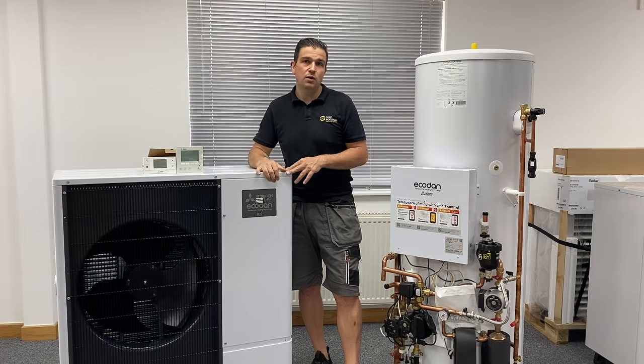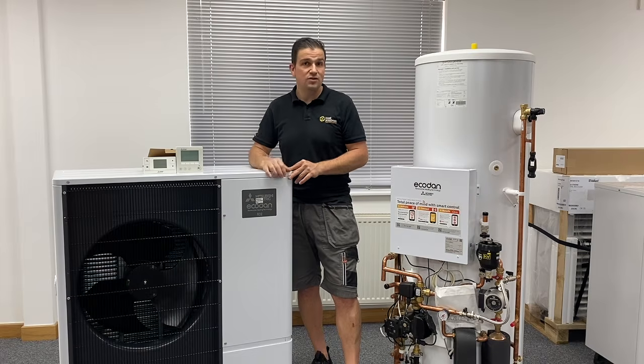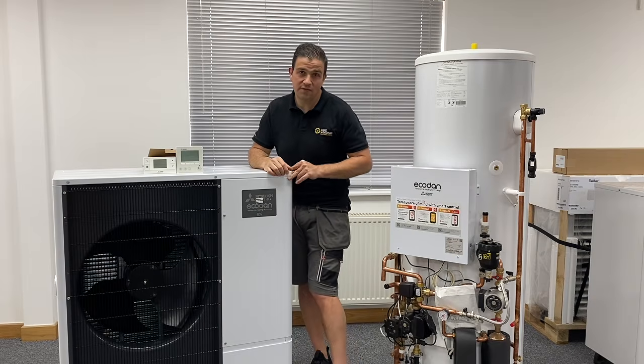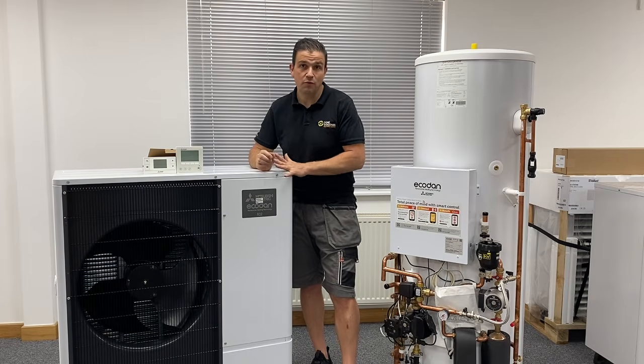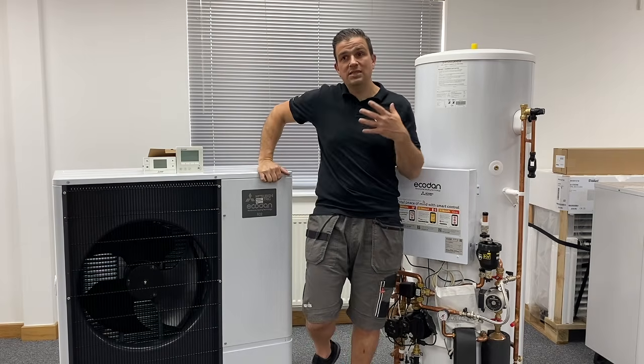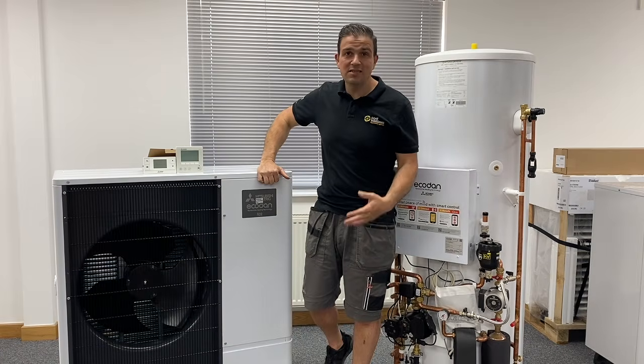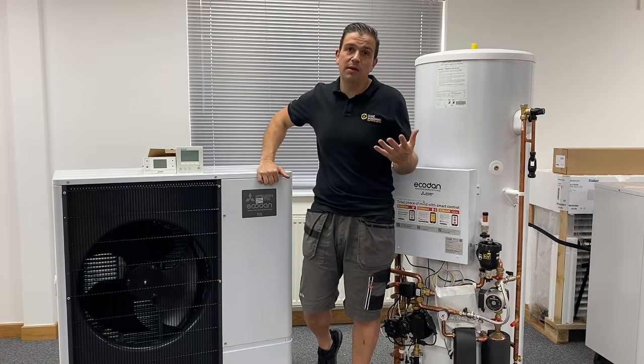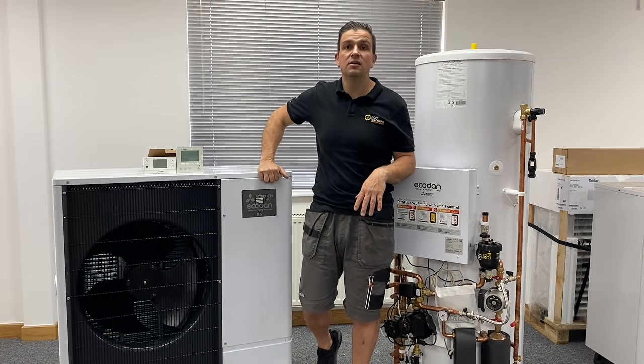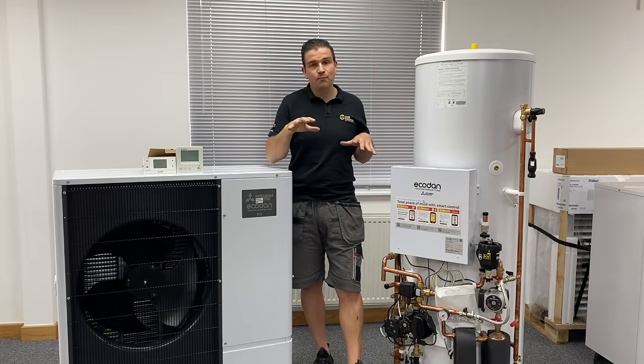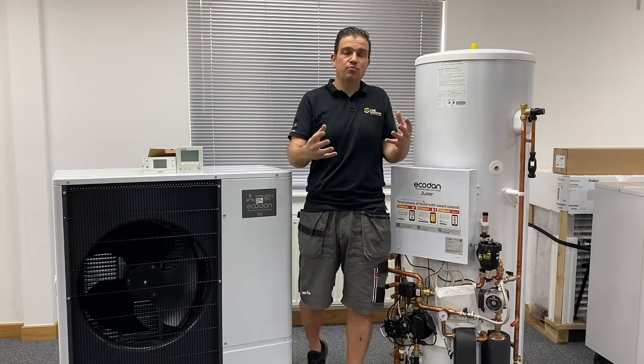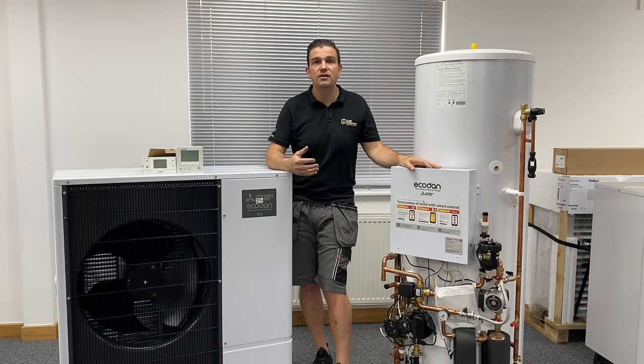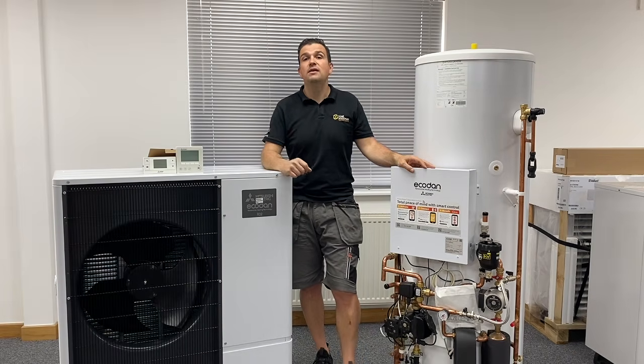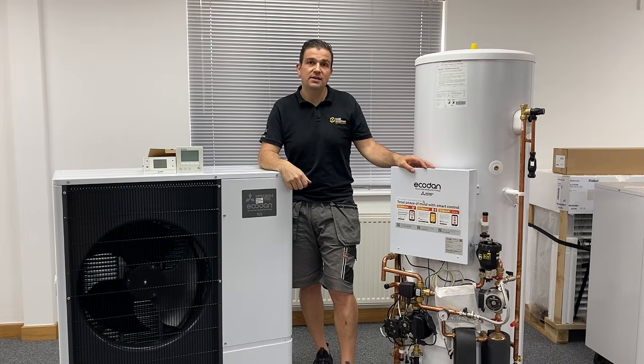We're confident that these work and that they will perform. We've installed them, we've had them in situations of very cold temperatures, and they have performed. If they don't, then it comes down to either a settings situation, or it may have been miscalculated on the heat loss. But there's always a way, and it's really down to the installation that provides you with efficient and on point heat pumps that will provide you with heating and the hot water that you deserve.